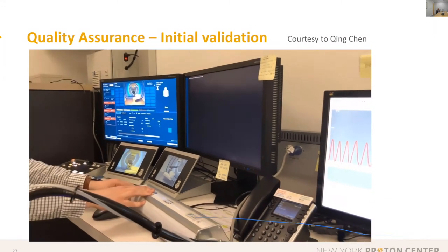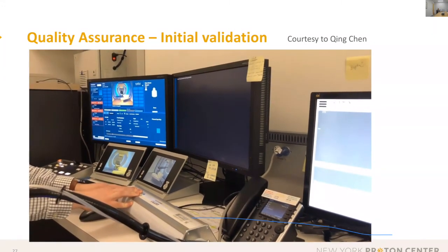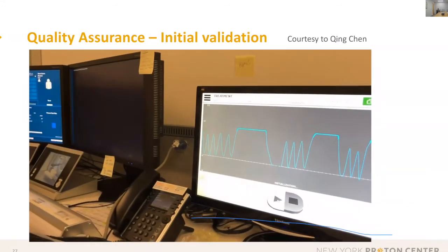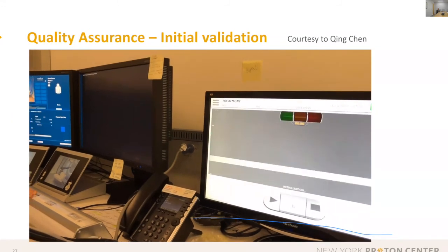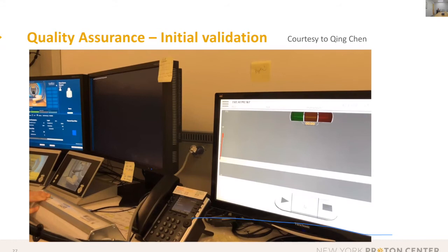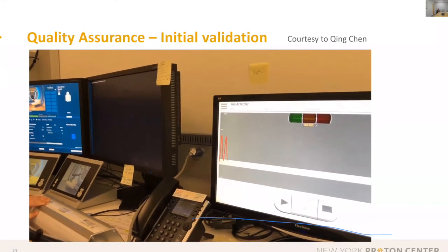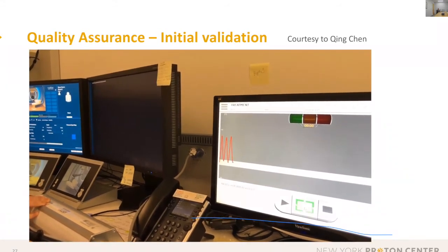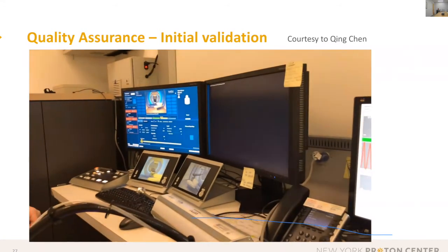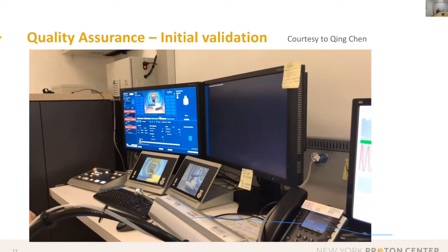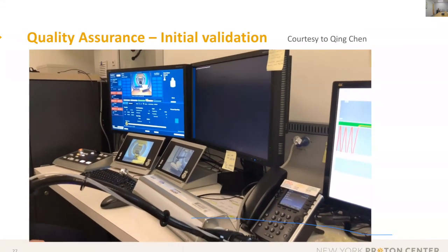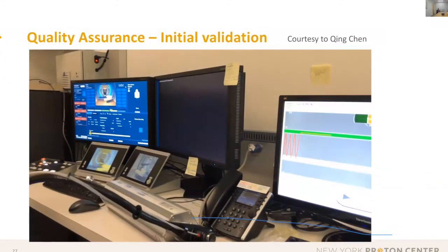Yeah, this simulates a very sharp drop off from the gating window, and the SDX system will basically show overflow errors. At the beginning, the proton beam would drop off, but now, after the fix, even if you stress the system very hard, the beam will automatically turn on. Yeah, this is just a demonstration of how this auto gating system is working.